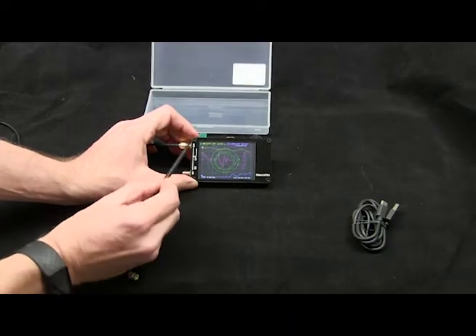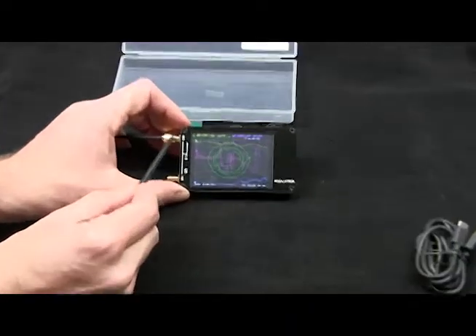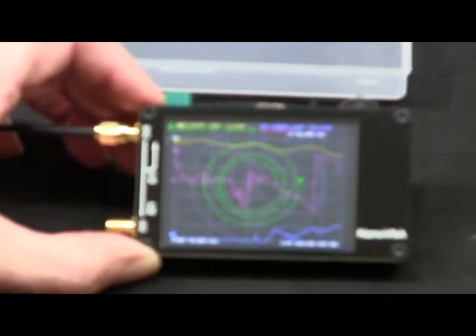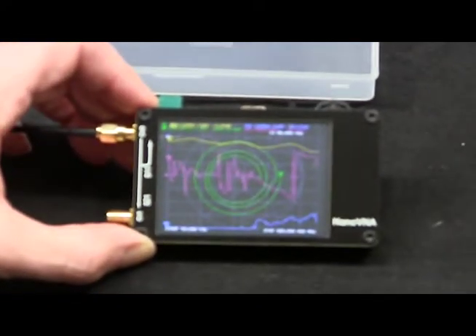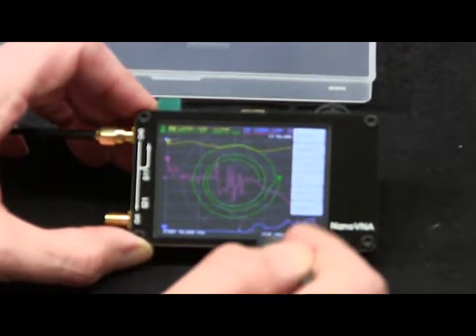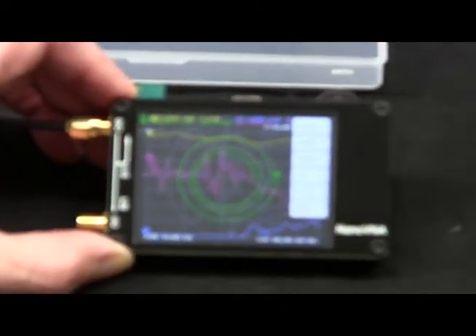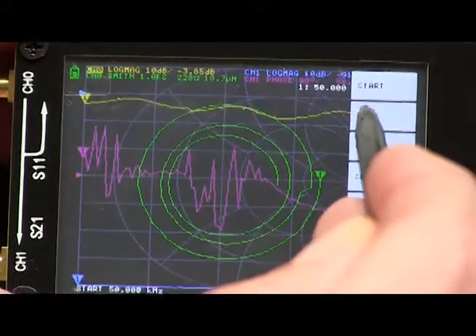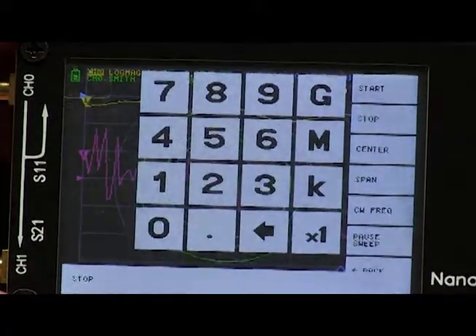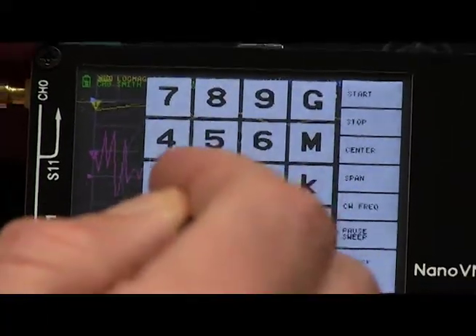And if you look here, you can see that the signal is going to go out of this channel, and that's by these 2 directional arrows, letting you know it goes out this channel and into this channel. Now what we want to do first, before we calibrate, is if we click anywhere, we can have the menu come up.